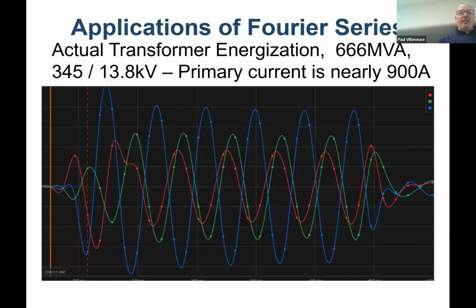And if you look back over here, you can only see that phase A, or whatever the blue one is, I don't know if that's A or C, that's the one that was kind of high. The other 2, see if I can show you this one right here. You can see that that's got some harmonic component. So that's the one that only had a 2nd harmonic that was high. So the Schweitzer relay didn't trip because it was blocked from operation. The GE needed 2 out of the 3 to show a 2nd harmonic current was too high. It didn't happen, so it tripped the relay.